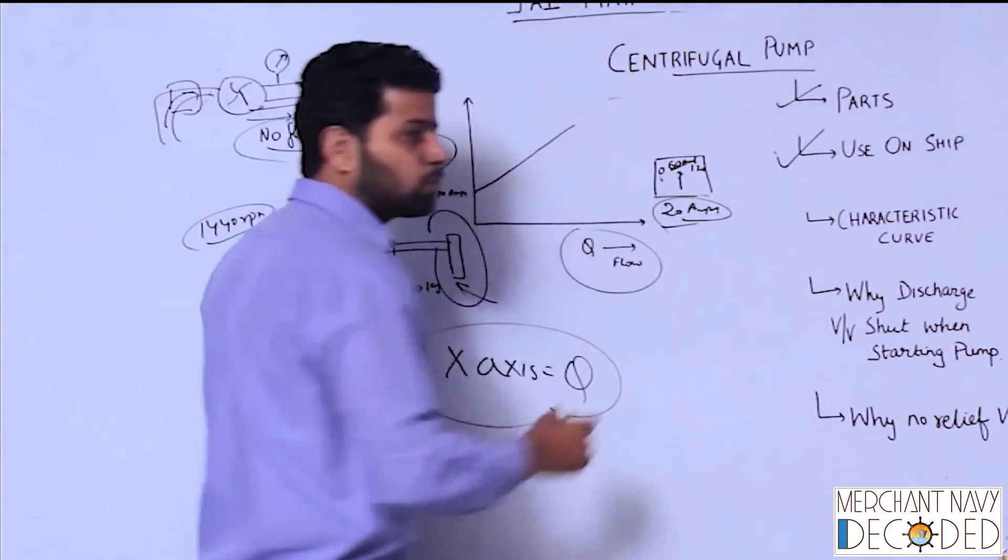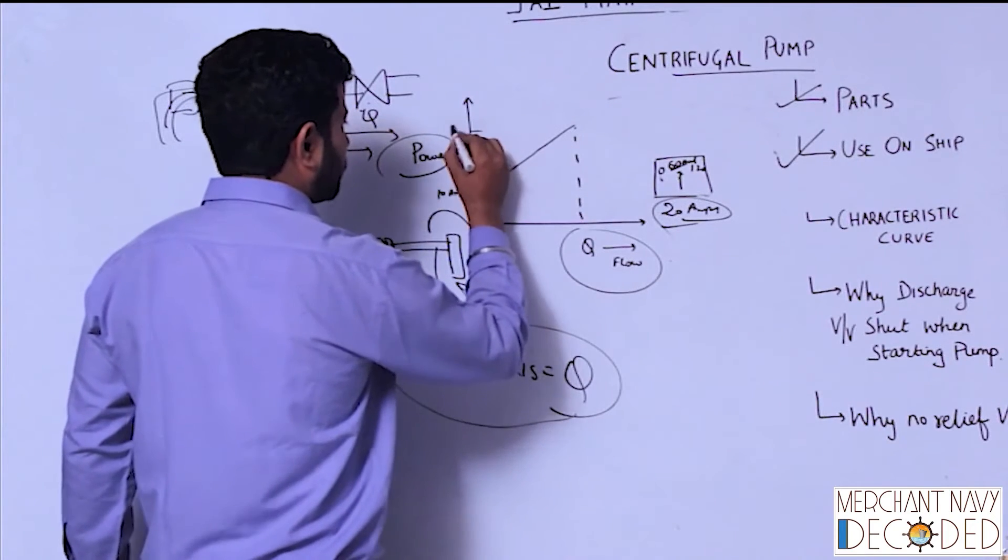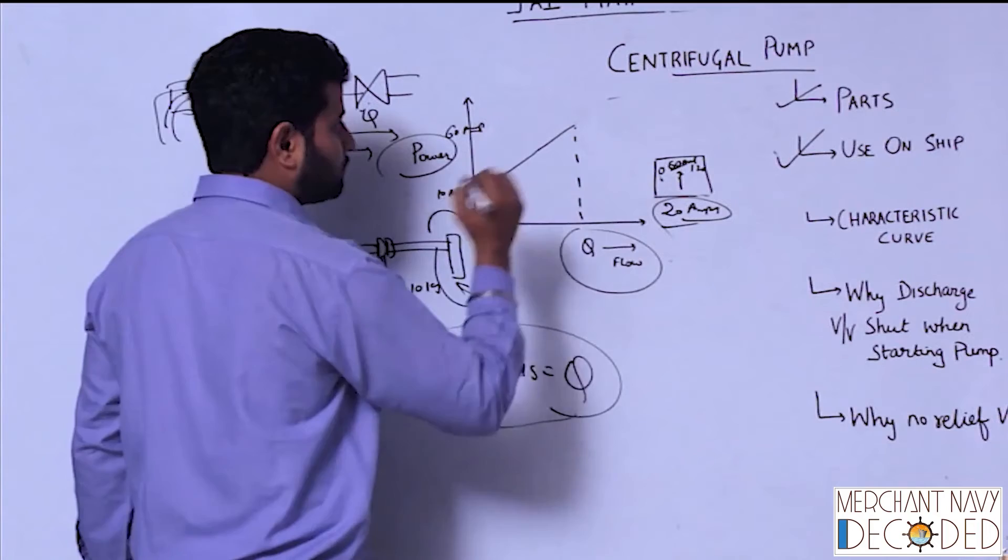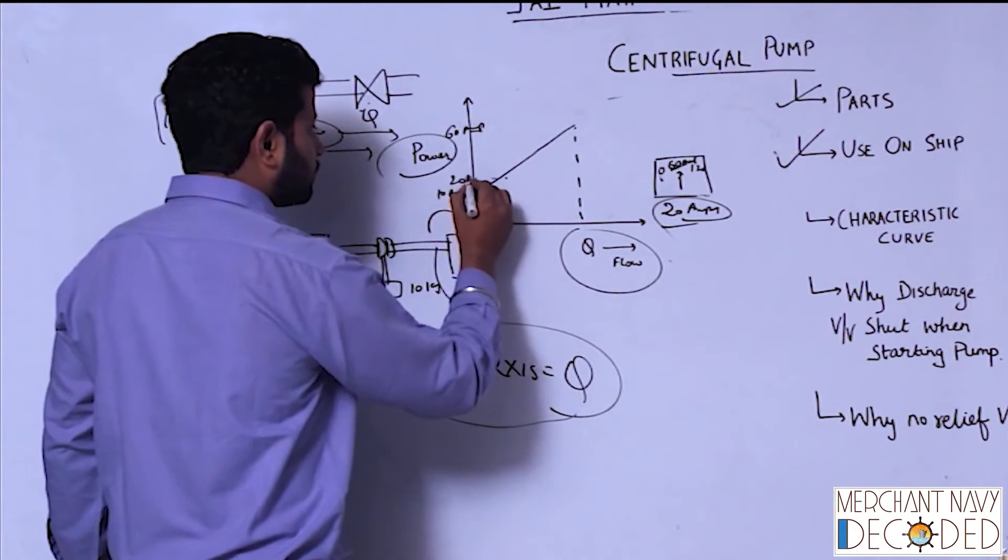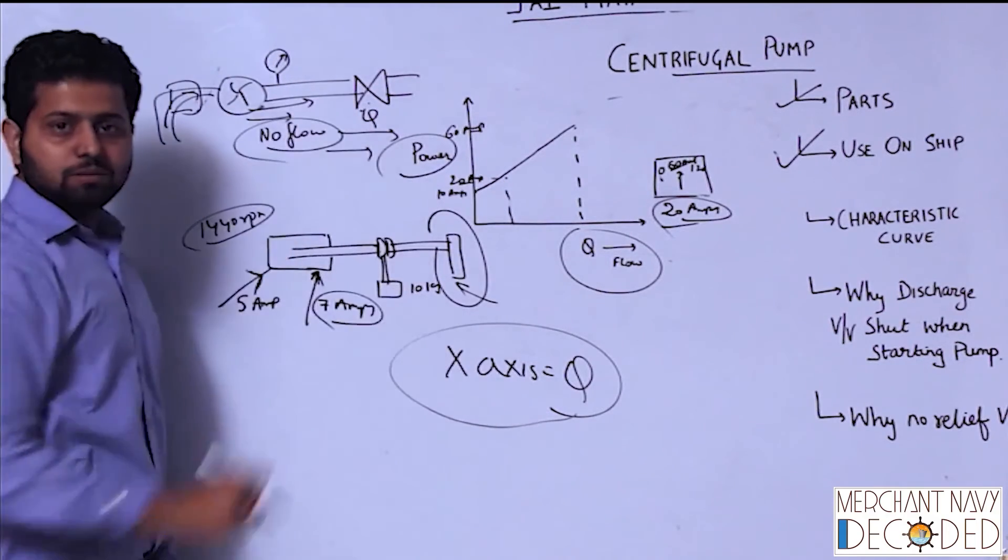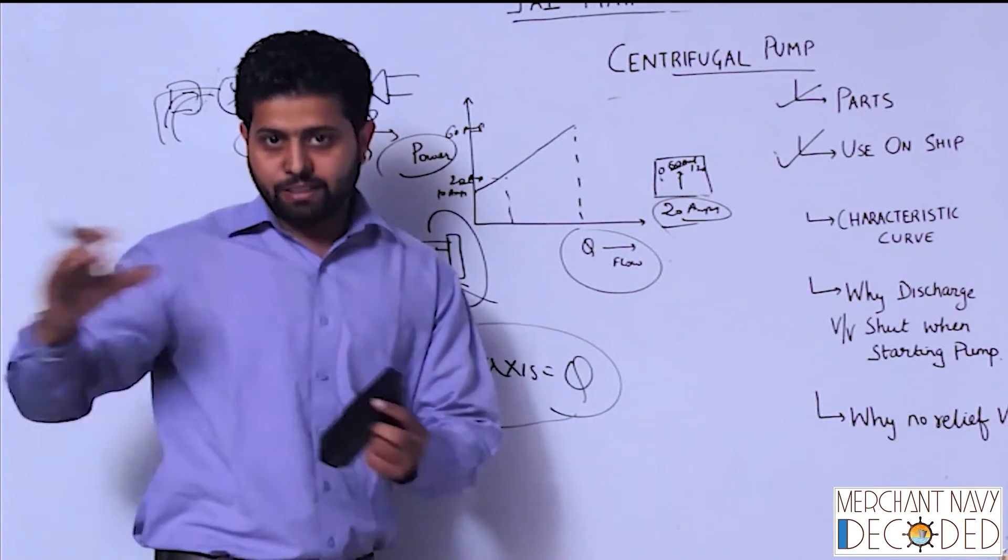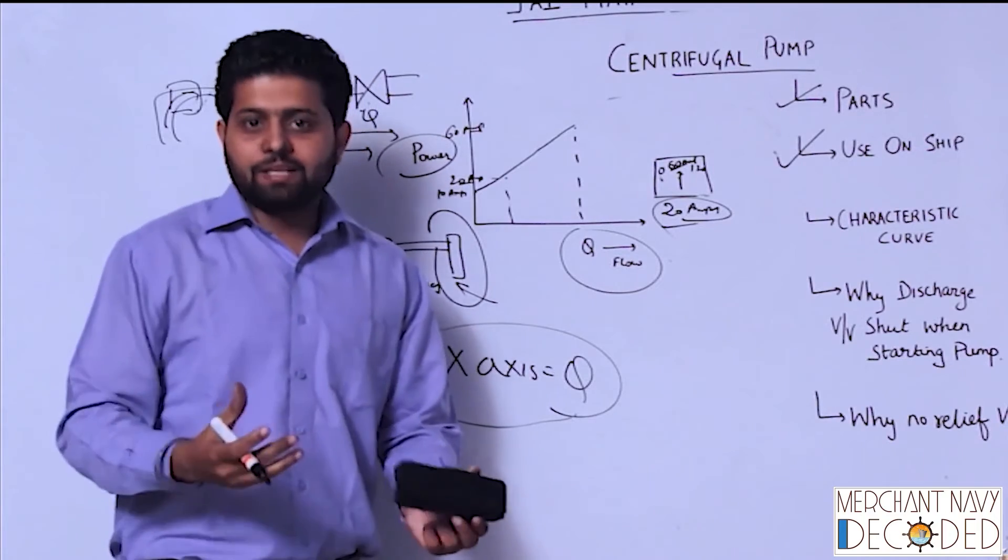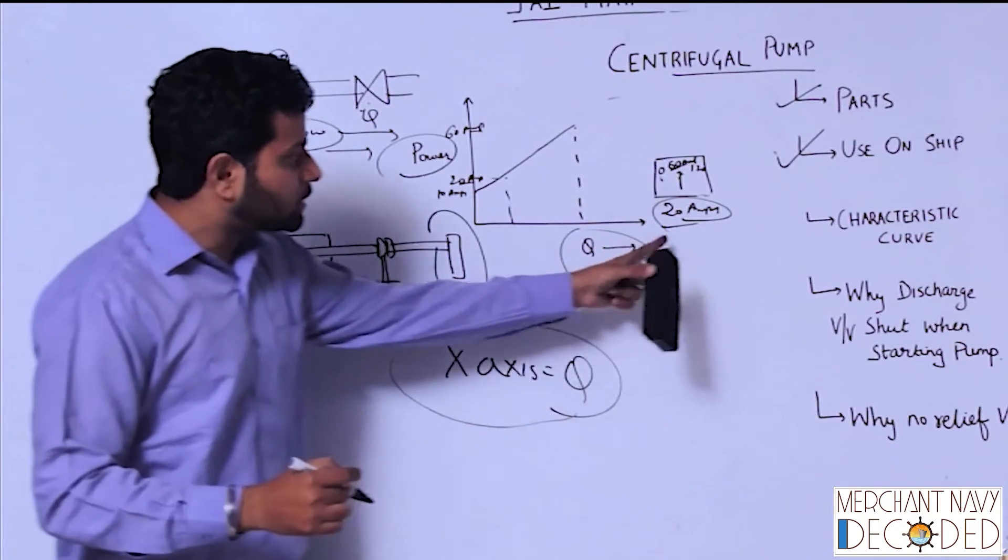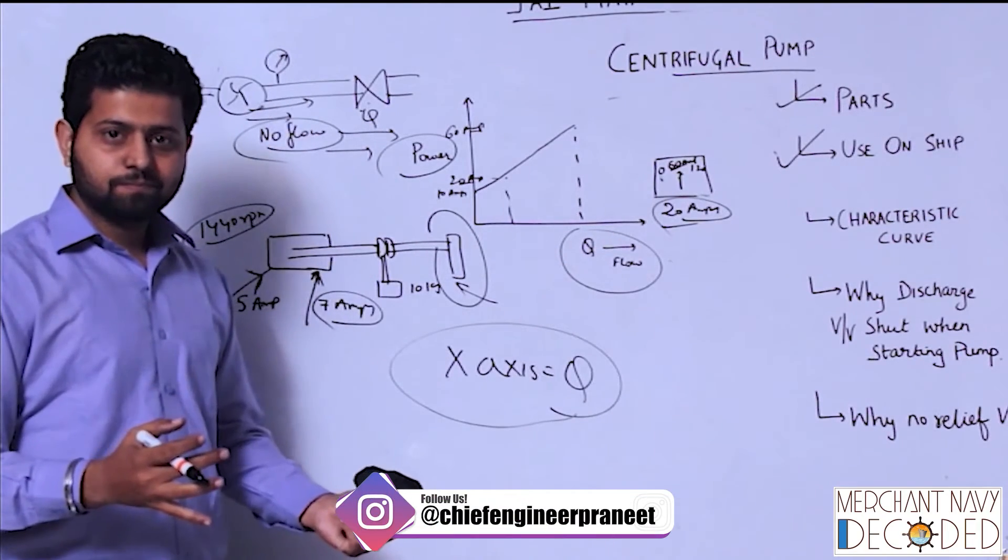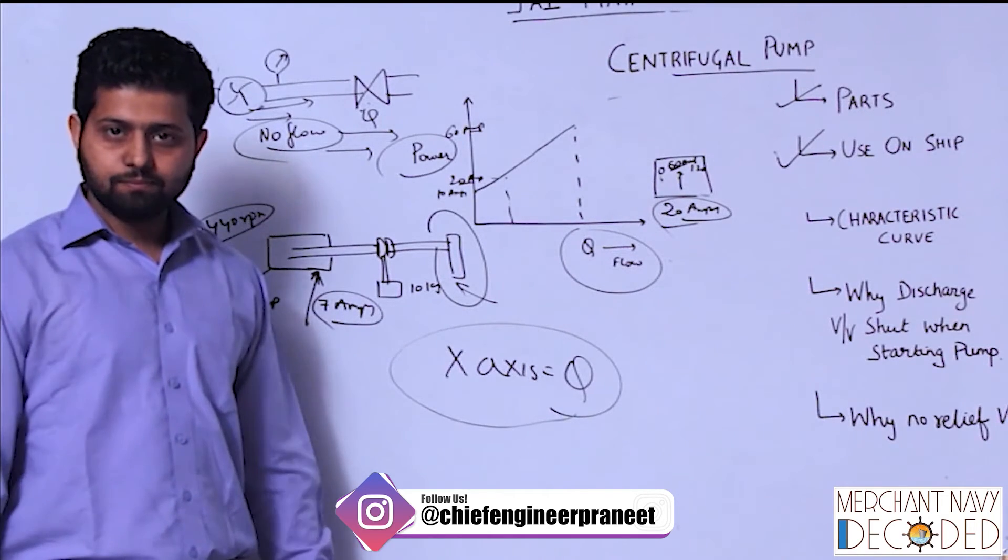From 60 amps it has become 20 amps because, say, it was taking 60 amps over here when Q was maximum, but suddenly you saw the filter has choked, there is no flow taking place. So if you are sitting, only if you know this thing, you know how it works. So centrifugal pump, flow matters. Clear guys?